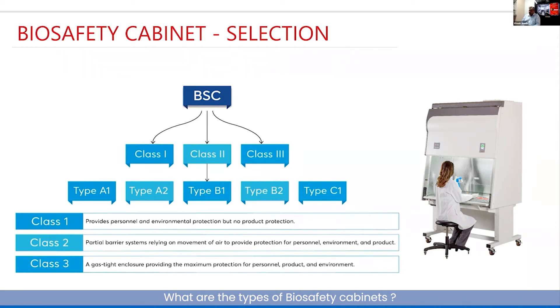People do not use Class 1 as a biosafety cabinet because it could potentially contaminate the sample, which could result in variable results when repeat experiments are performed.